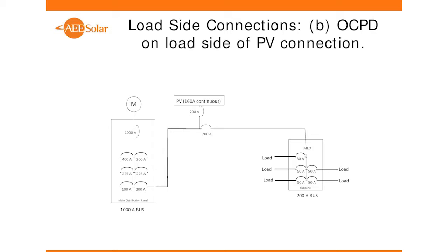Now, we could put it in this panel over here, but some wise ass could come along and argue, what if somebody taps this conductor in here and brings some extra load in here? So by putting it at the junction where we bring the PV in, since we're already going to have to do a bunch of electrical work at that point anyway, to interject yourself into a feeder is not a simple task. You're going to have to be doing a lot of electrical work in that area, so installing a new circuit breaker in there is not going to be that big of a deal. And we're doing it because it's saving us tons of money compared to doing it anywhere else in the system.